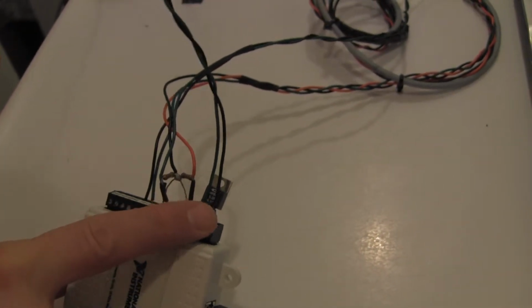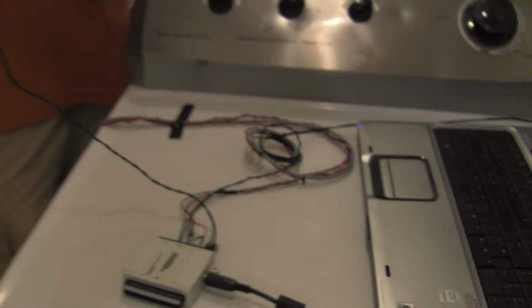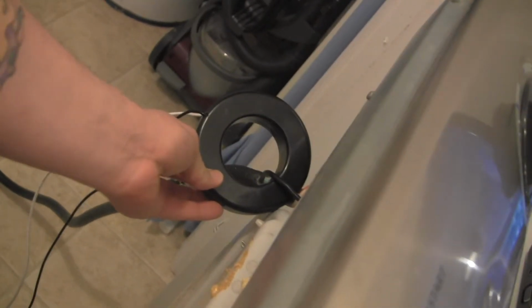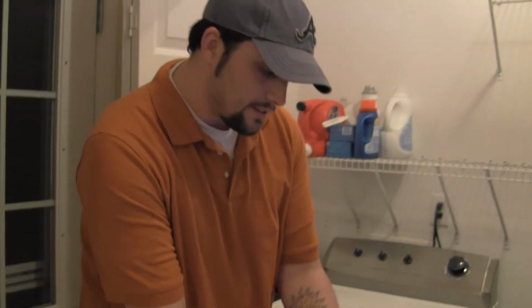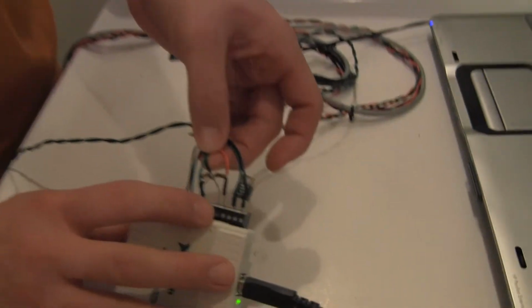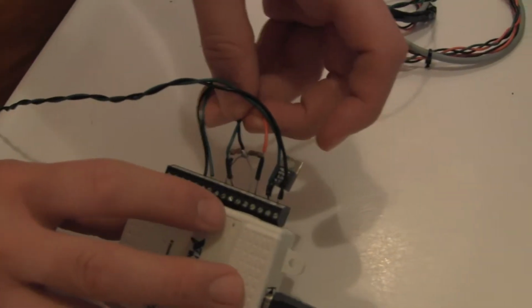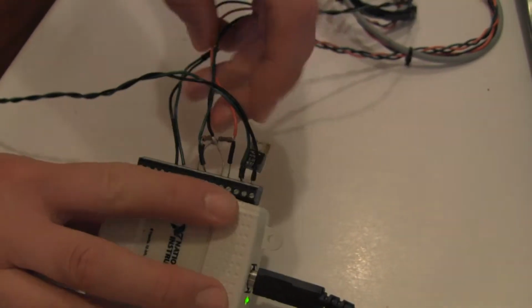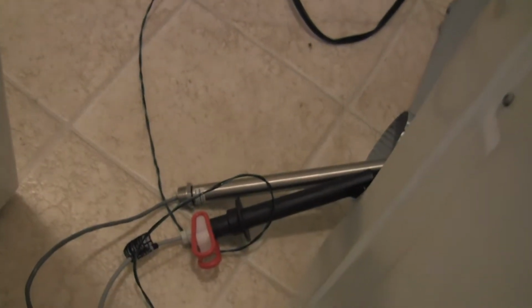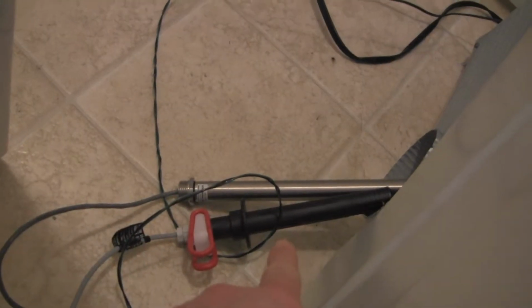It has a resistor right here, a power resistor, and it's connected to, if you come around back here, this current transformer right here. We took one of the hot legs of the 240 coming into the dryer to put the current transformer on. Now the next channel that we'll talk about is AI1 and AI2, actually, go to a temperature probe. The temperature probe is put into the exhaust right here, this stainless steel probe, and this black probe here is the wind speed probe.